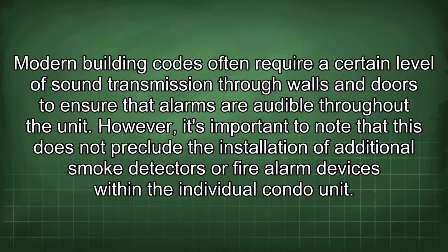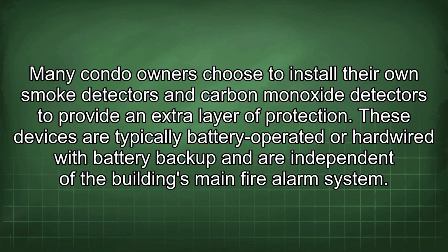However, it's important to note that this does not preclude the installation of additional smoke detectors or fire alarm devices within the individual condo unit. Many condo owners choose to install their own smoke detectors and carbon monoxide detectors to provide an extra layer of protection.